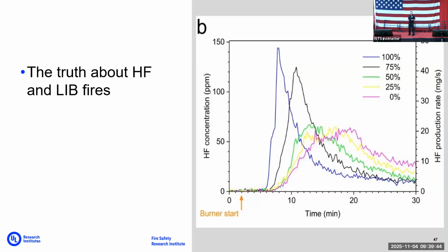If you break it down even further, if you're in there for an hour doing overhaul and you didn't properly ventilate the area, or didn't get all the batteries out of the environment before you cleared it okay to enter, even at 32 parts per million, you're going to consume your lethal dose of HF. For HF, per the MSDS criteria, 30 parts per million is the threshold that means you need to be on air. So at 32 parts per million, being there for an hour, you're going to consume your lethal dose of HF, which could cause significant health effects down the road.